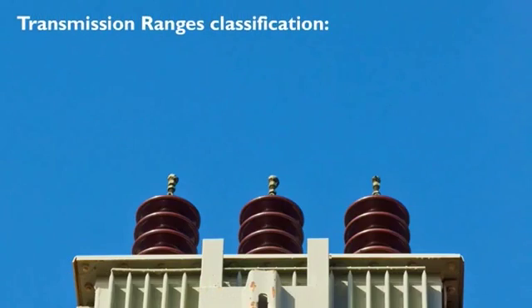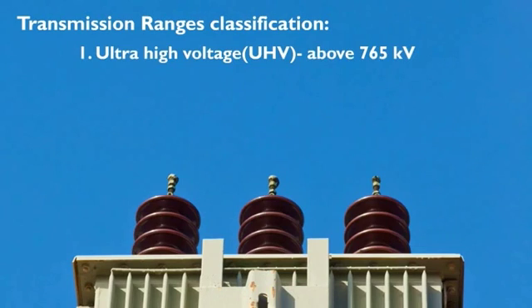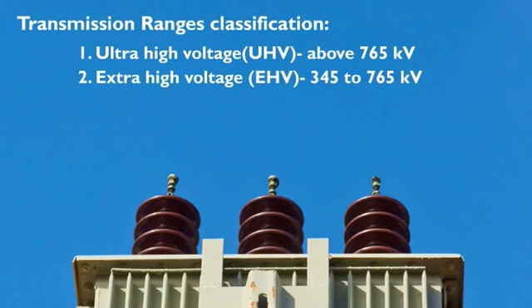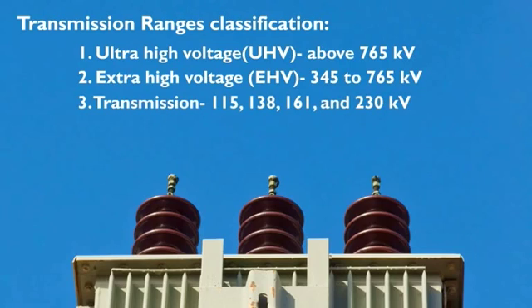Several terms may be used to classify transmission ranges, such as: 1. Ultra-high voltage, UHV, above 765 kV. 2. Extra-high voltage, EHV, 345 to 765 kV. 3. Transmission, 115, 138, 161, and 230 kV.